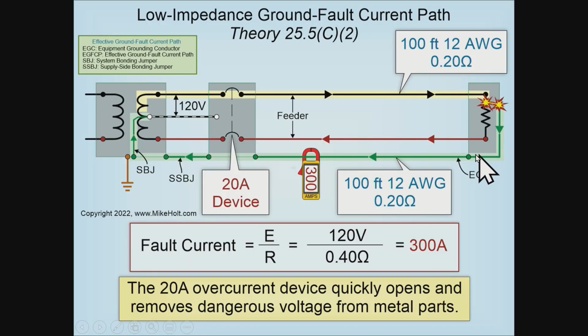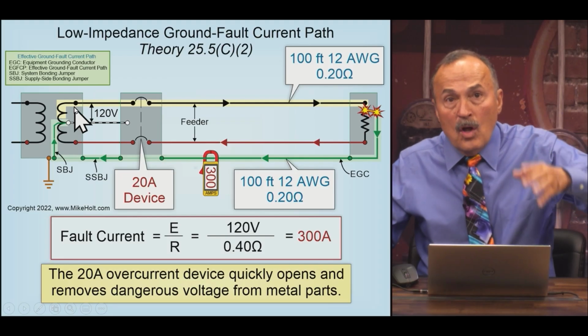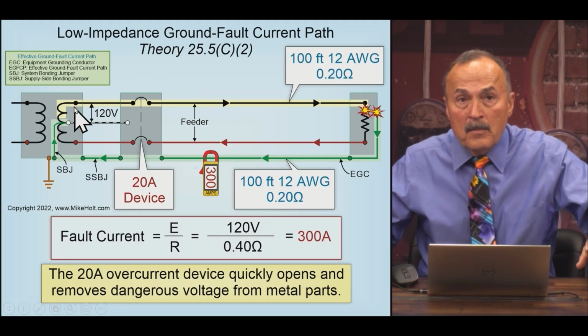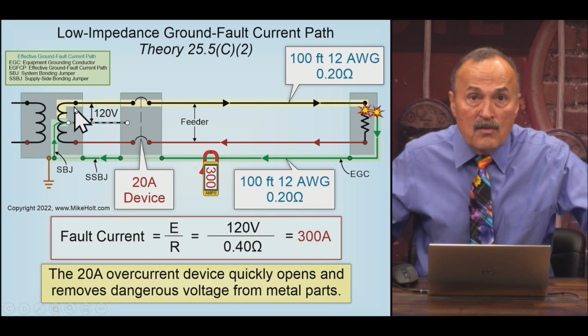But the important part is this. We do need to make sure that there's a fault return path to go back. Right here, take a look at this. This is the code. It says, listen, you have to size this wire. You have to make these connections. You have to do them in certain ways. We have to do the best that we possibly can to have the low impedance fault return path to facilitate the opening of the overcurrent device.